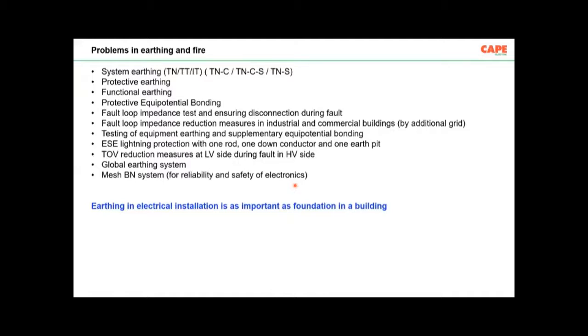So a good earthing means you have to have a very good system earthing, protective earthing, functional earthing, protective equipotential bonding, fault loop impedance and reduction measures with a tested system, TOV reductions, temporary overvoltage reductions due to a high voltage fault, so nothing should fail on the LT side, a mesh bonding network and so on. This is what earthing in a modern building is about. Earthing in electrical installation is an important subject. It is as important as a foundation in a building. If you construct a building without a foundation, you can be sure that the life of the building is very short.